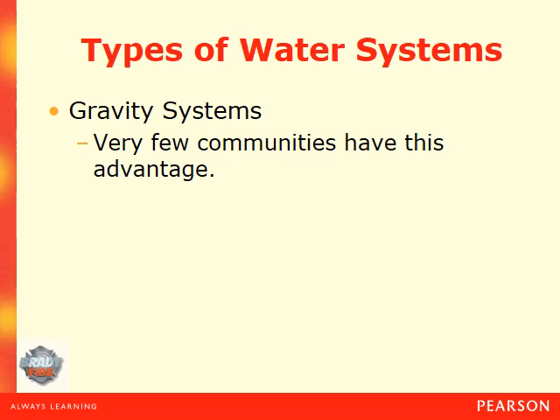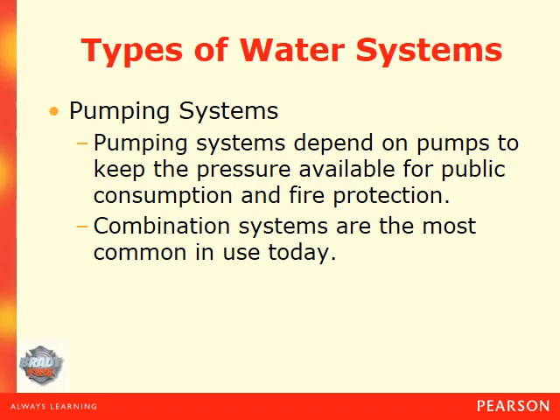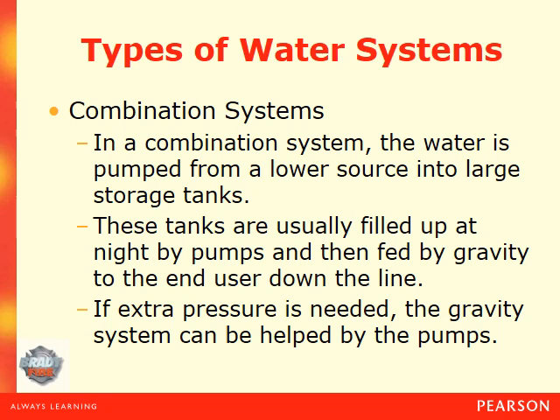Unfortunately, few communities have a gravity system. A pumping system depends upon pumps to keep the pressure available for public consumption and fire protection. Combination systems are the most common used today — they use a cross between gravity systems and pumps to feed the municipality and ensure that water demands are met. In a combination system, water is pumped from a lower source into a large storage tank. These tanks are usually filled at night by pumps and then fed by gravity to the end user.